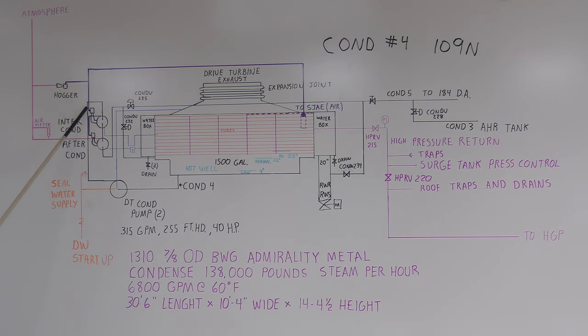It would pull the steam to be condensed. The condensate from here went down through a loop seal and back to the surface condenser. This would pull it down really pretty good on the vacuum. Then the second stage would pull it down the rest of the way. So you had another steam jet air ejector take everything from this one, pull it through another stage.